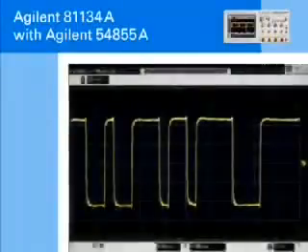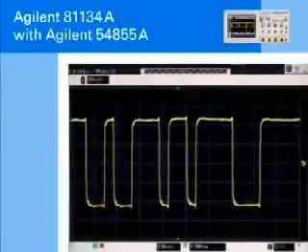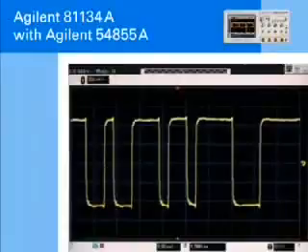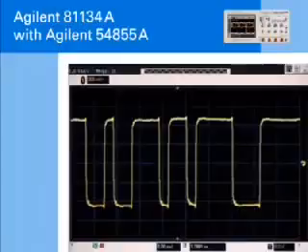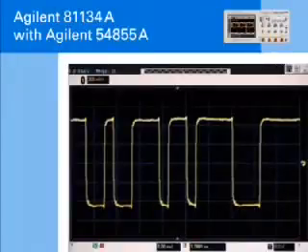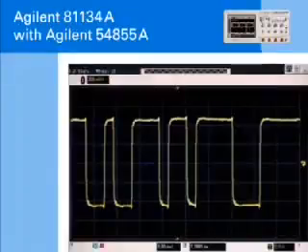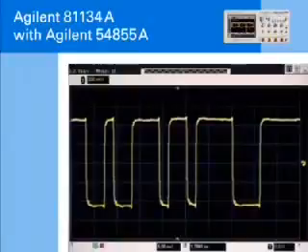With its burst capabilities, the Agilent 81134A allows you to test your serial devices by generating special data patterns such as initialization patterns or burst data transfers in order to test how the device under test really behaves. The data that is set in each burst can be set in the data pattern screen, including data pattern length and the bit sequence.